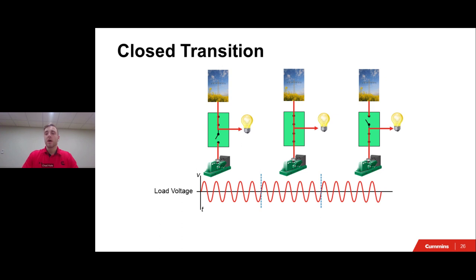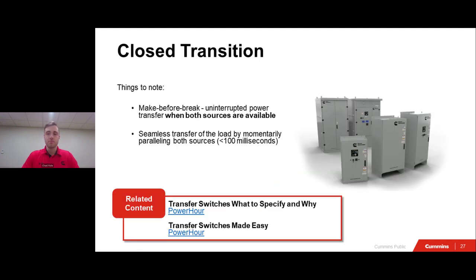So you can see you have the normal and backup in the middle. It closes onto both very briefly. And then on the far right there, you can see that it has finally closed on to the emergency power source and then opened itself to the normal source. And then there is hardly any interruption of power to your loads. So once again, some things to note are that this is a make before you break transition, which is completely different than your open, which is a break before you make.